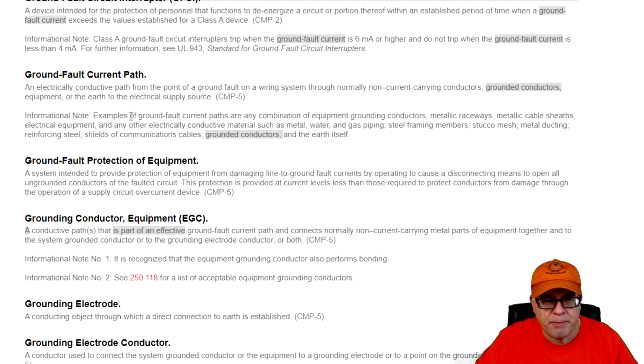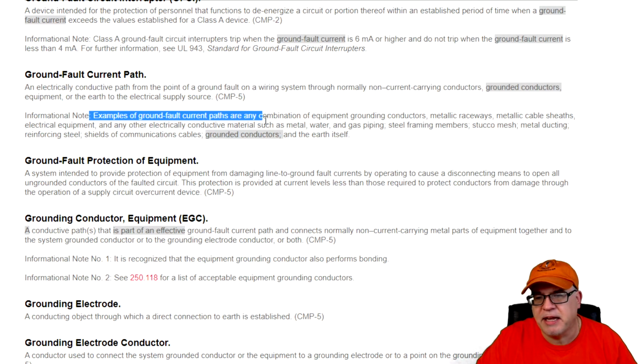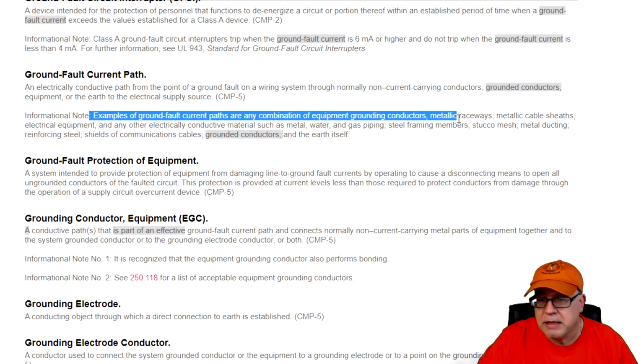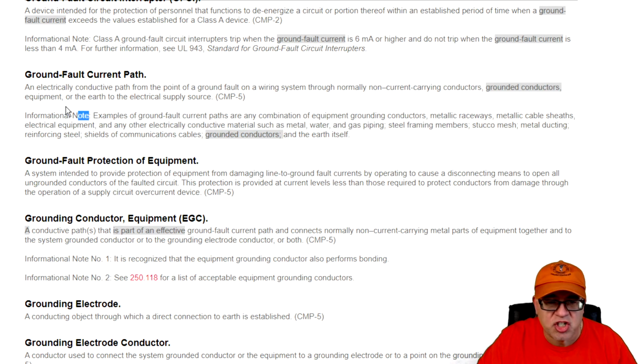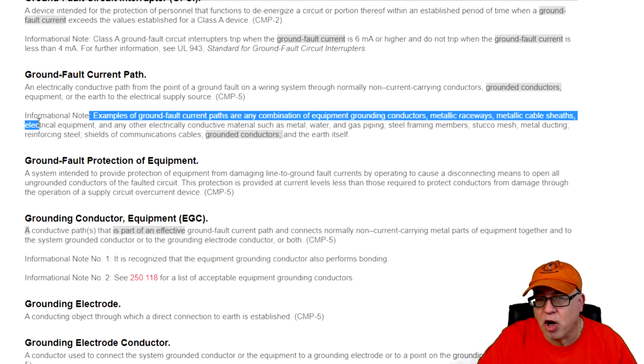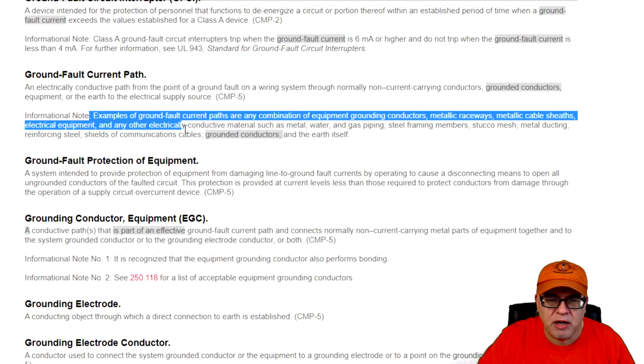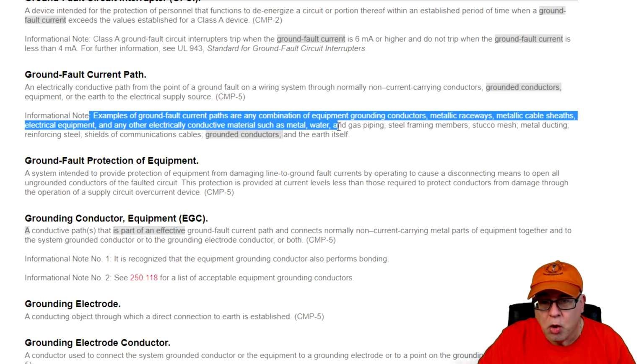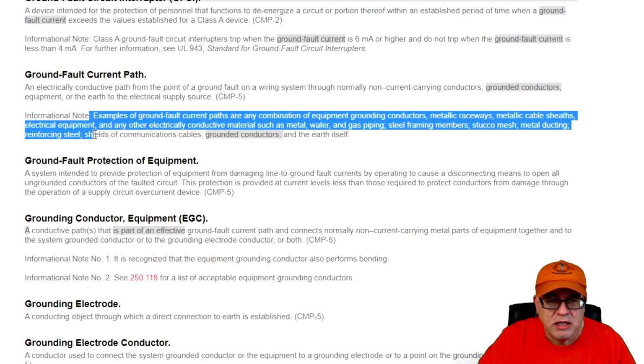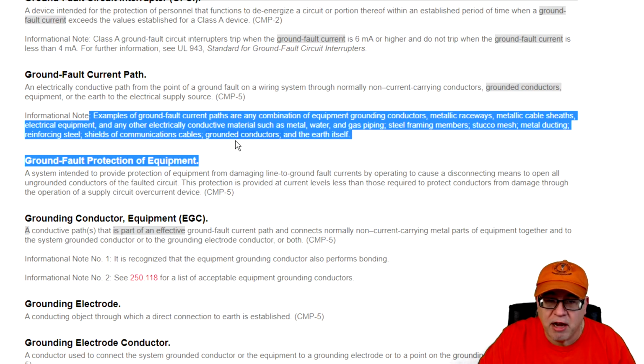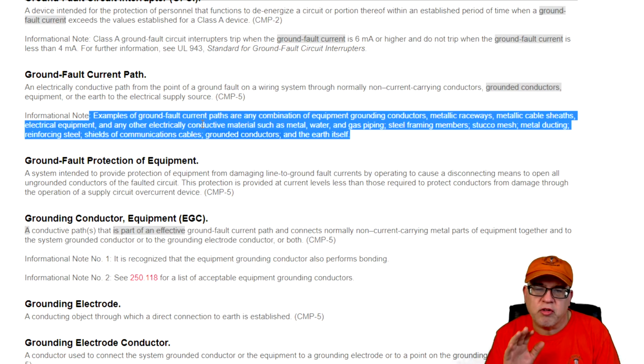So it says here an example informational note. It says, examples of ground fault current paths are any combination of equipment grounding conductors, metallic raceways, metallic cable sheathing, like an AC cable where the armor is used as an effective ground fault current path, and any other electrical conductor materials such as metal water, gas piping, steel framing members, stucco mesh, metal ducting, reinforcing steel, shields of communication cables, grounded conductors, and the earth itself. All of those things, current will travel on that path.